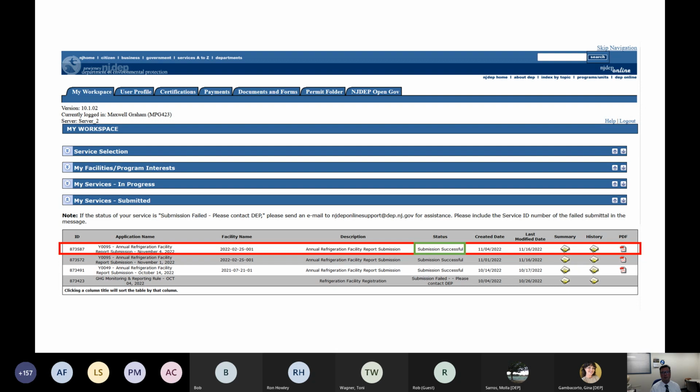So that's going to be the distinction. Yes, chillers have to be reported, but also refrigeration systems have to be reported. What does not have to be reported is an air conditioning system that has nothing to do with the chiller. Okay, what's the second part of that? The second part was all refrigerant, regardless of type, needs to be reported. Again, no. Only refrigerants that have a global warming potential of 150 for the 100-year time frame.